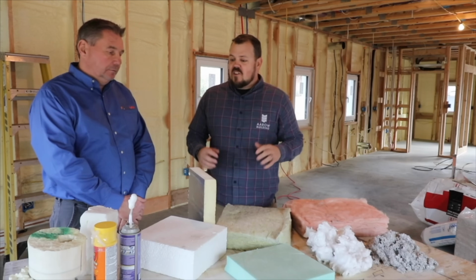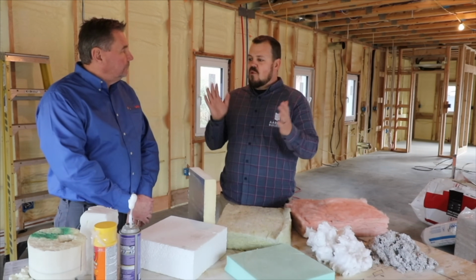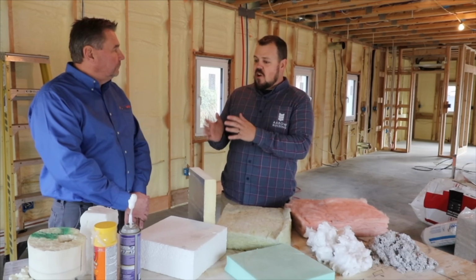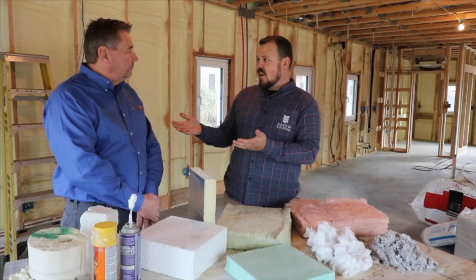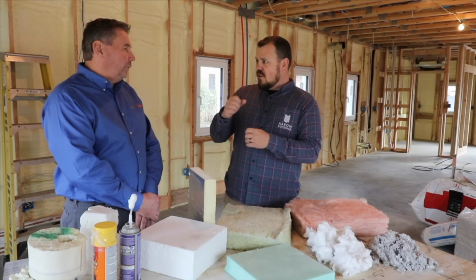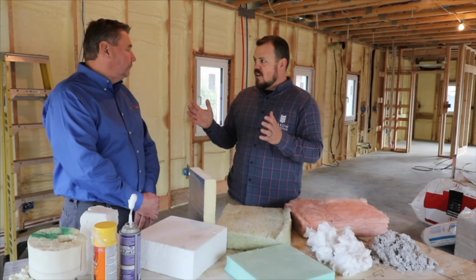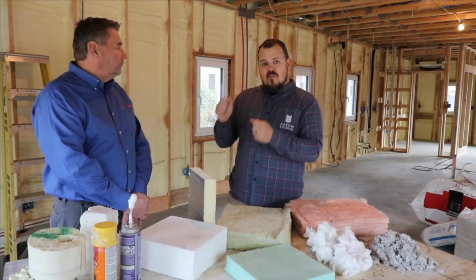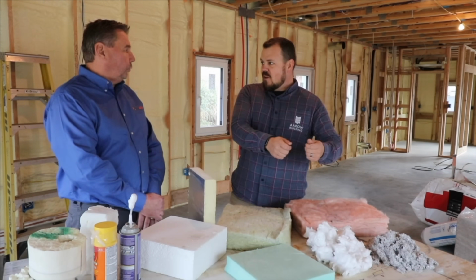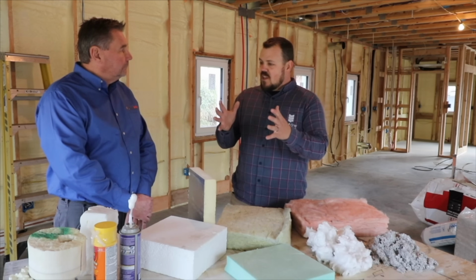Okay, so the conversation about insulation, after we know what our proportions might be for something like this, we can talk about code, which in our market, Climate Zone 4, is an R-19 for walls, and I believe an R-40? R-38. No, it's 38. Well, you may be 40 here. And so there's different ways to get there. The code doesn't read, put this kind of insulation in. The code reads, put this much R value in. And so the conversation should start with R value once we have that beginning out of the way.